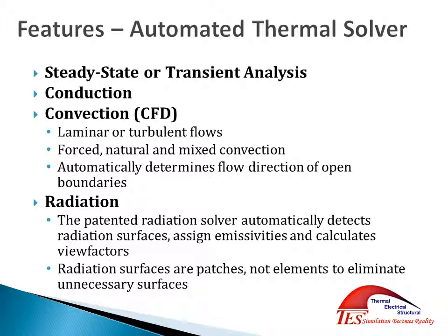So our solver allows for both steady state and transient analysis. It does solve conduction, convection, and radiation. You can look at forced, natural, and mixed convection. And as I mentioned with the radiation, the patented part of it actually is that you're patching elements together. So you're not solving every element individually. You're actually solving a group of elements at once that will then have a similar temperature, and it'll use the average temperature of that for the radiation network, which allows it to solve much faster.